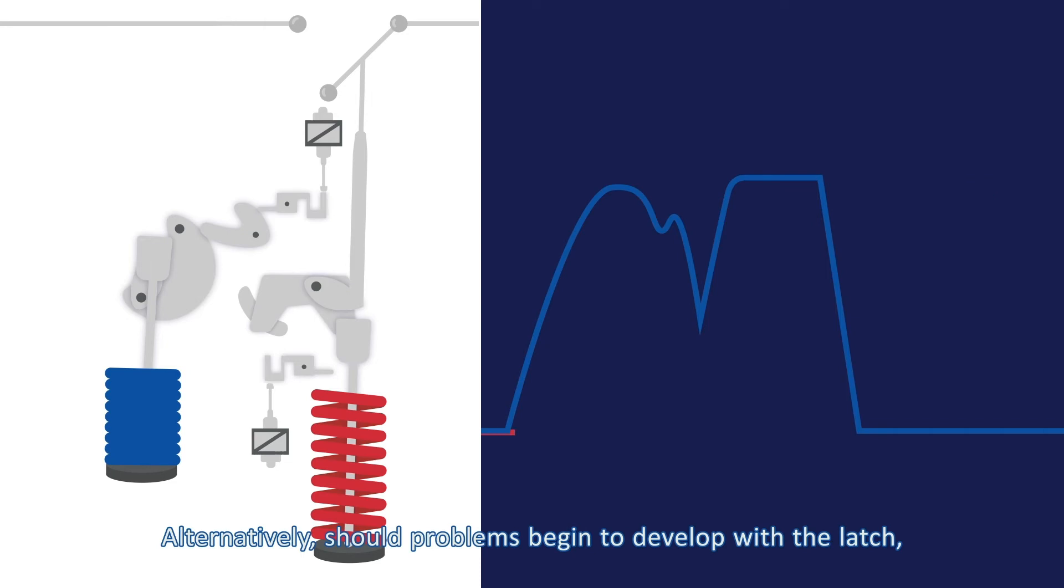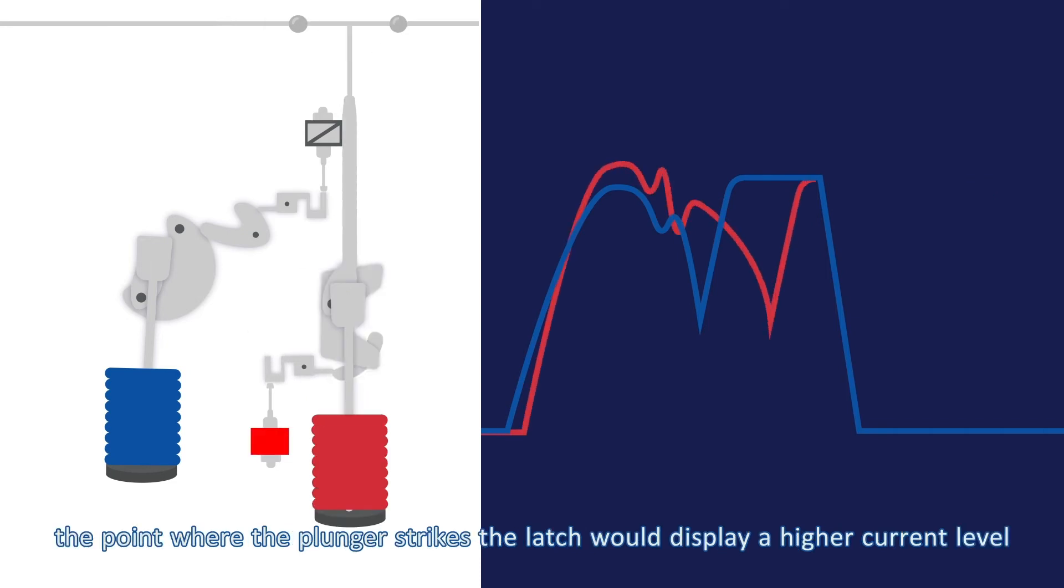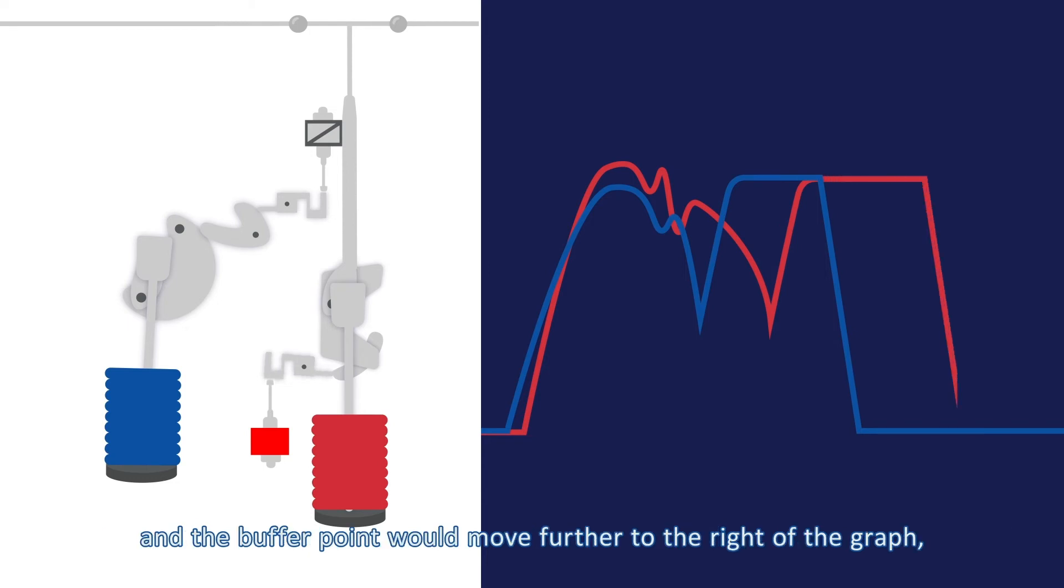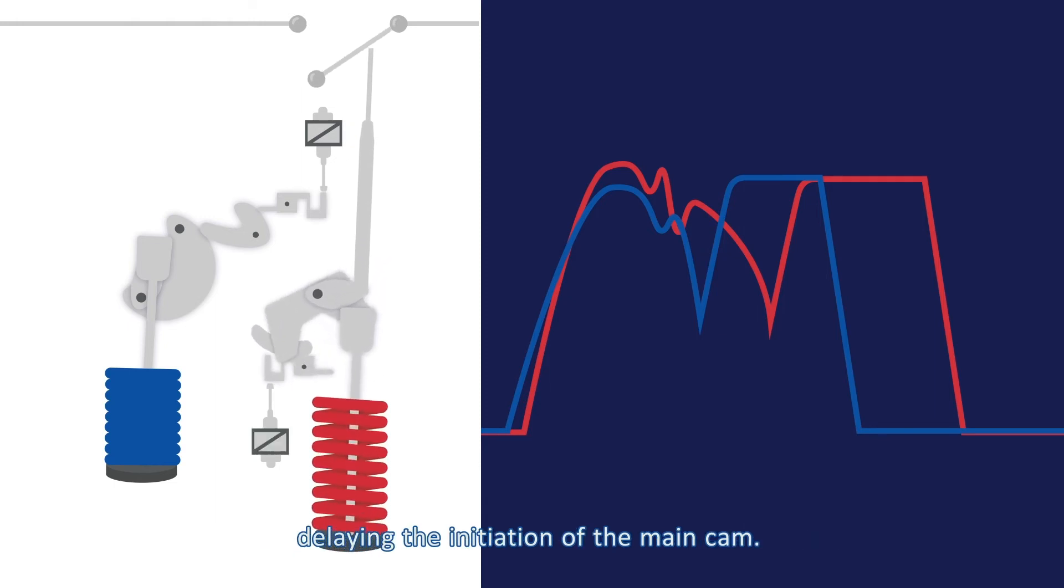Alternatively, should problems begin to develop with the latch, the point where the plunger strikes the latch would display a higher current level and the buffer point would move further to the right of the graph, indicating that the breaker took longer to release the latch, delaying the initiation of the main cam.